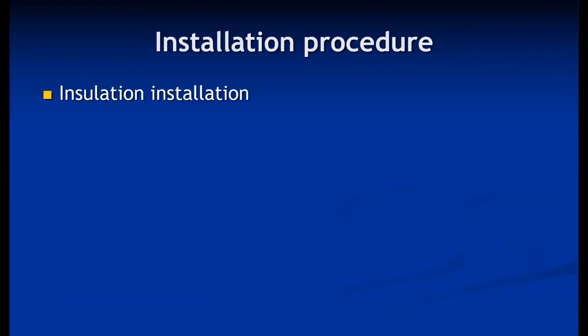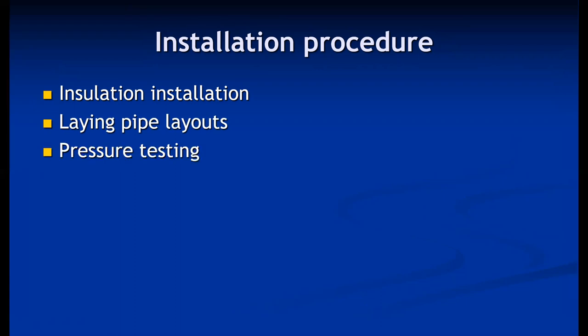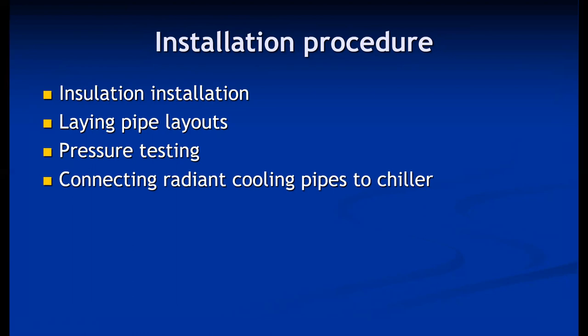As far as installation procedure is concerned: first, insulation is installed; then laying out pipe layouts; then pressure testing is important because leaks are not allowable — in case of a leak, surfaces become wet, leading to fungus and bacterial growth. Leak testing is an essential part of the piping installation. Finally, connecting radiant cooling pipes to the chiller and commissioning of the system are the important steps of radiant cooling system installation.